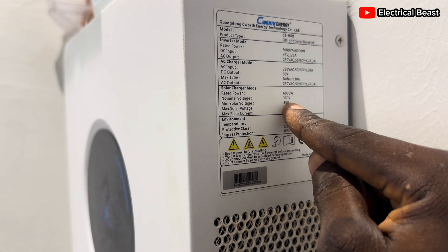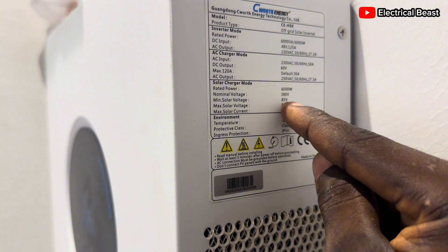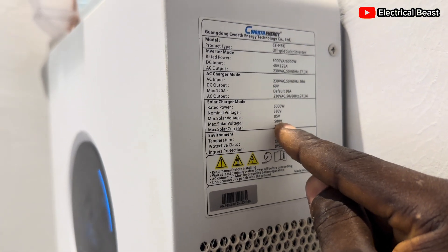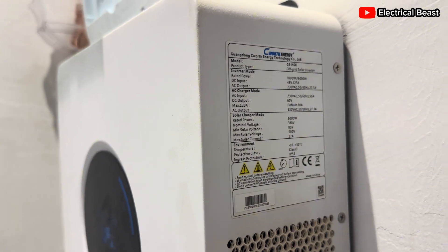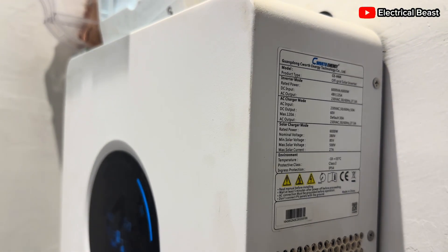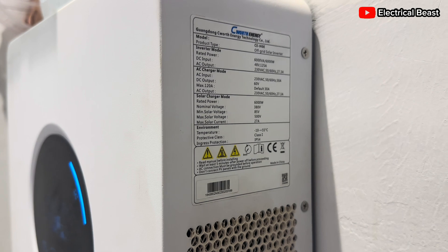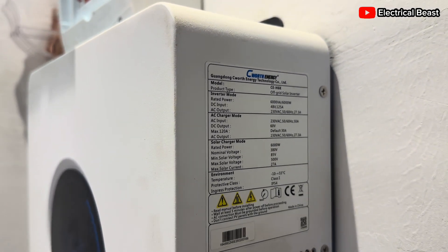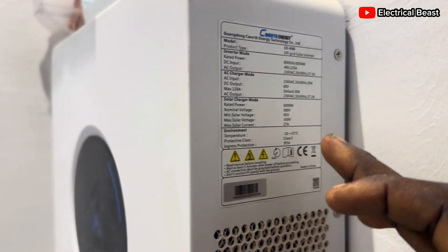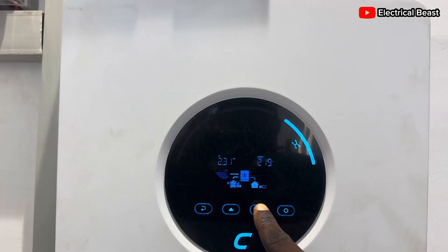The minimum solar voltage is 85 volts, so maybe two panels could work, but it should not exceed 500 volts. The maximum solar current is 27 amps. You can connect 12 panels — 6 in series and two strings in parallel — because one panel's current is about 13 amps, giving 26 amps. Factoring in losses you get around 20 amps, safely within the 27-amp limit. I personally don't like to do parallel connections unless there's a clear need.